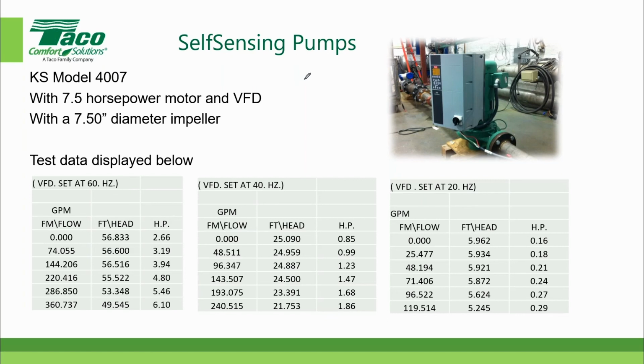So what is the lowest speed the motor pump can be worked at? In a self-sensing pump, we do not recommend that we go below 20 hertz. So that's the minimum speed, which is 1/3. If the maximum is 60 hertz, the minimum speed is 20 hertz. So 1/3 the maximum speed is the slowest we recommend that you operate that pump. The self-sensing pump, by the way, physically comes from the factory with a limit of 20 hertz at the lower end. So if you change those parameters, then essentially you're operating the pump outside of what the factory recommends.